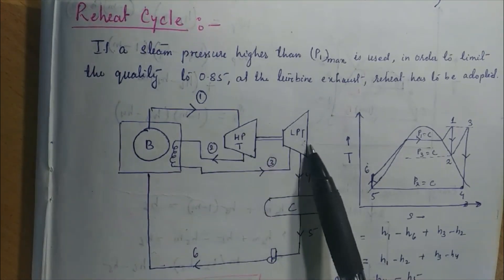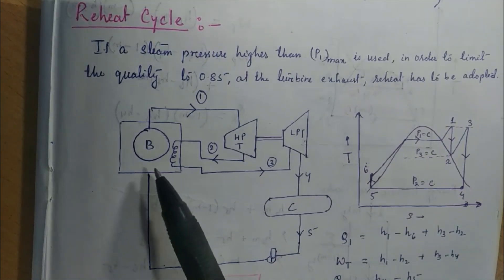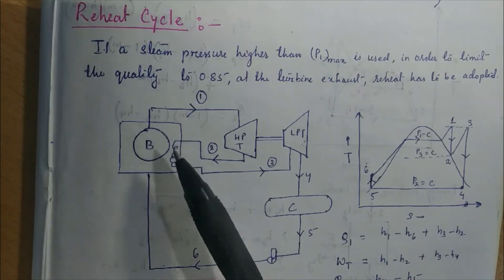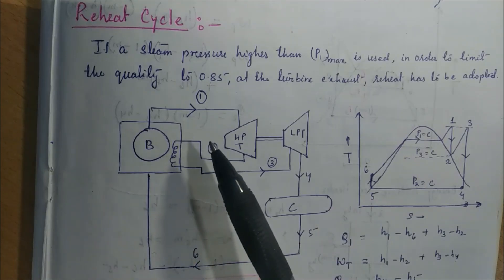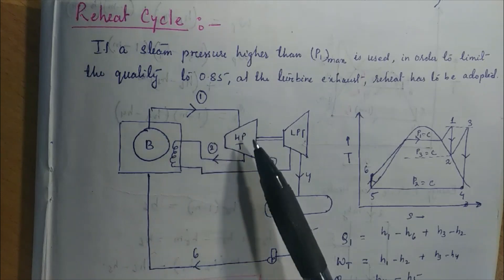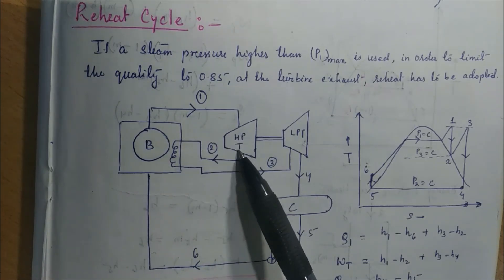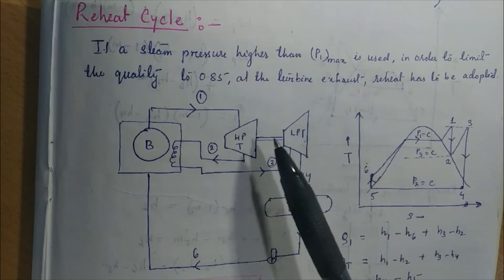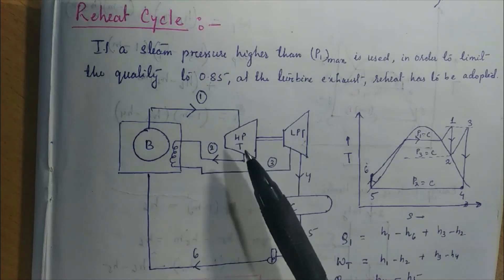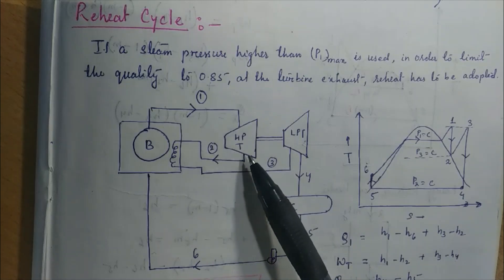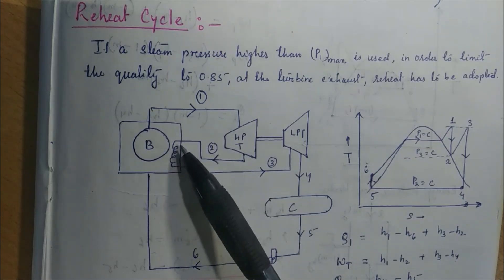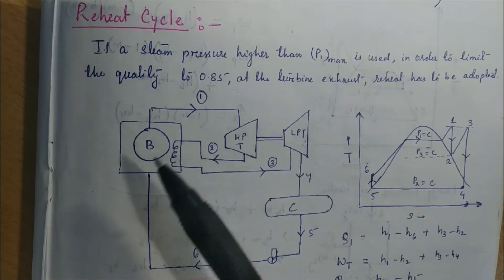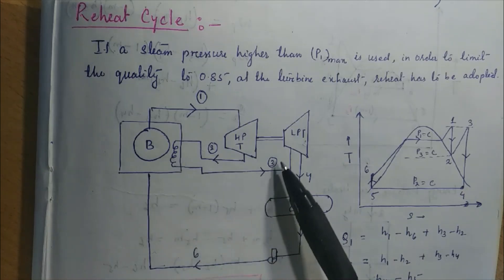The system consists of a boiler, high pressure turbine, low pressure turbine, condenser, and pump. In the boiler, we supply heat energy Q1 to generate steam from water. The steam is superheated and fed to the high pressure turbine. After performing work in the high pressure turbine, the steam is exhausted and fed to the reheater coil, which is connected to the boiler chamber, where the steam is again heated.